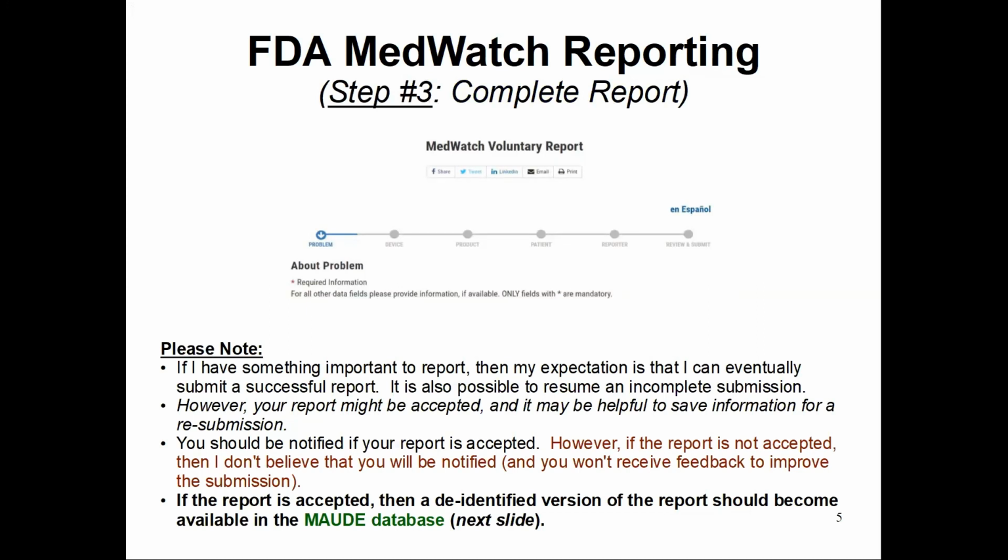And to be clear, the FDA does not want you to resubmit the same report again. So if it's been more than a few months and you haven't got notification it's been accepted, then you can consider thinking about ways you could collect more evidence or explain yourself better and resubmit. But I would take some time and think about what could be changed in the report. And the next slide will relate to the FDA MAUDE database, which is where, if the report gets accepted, a de-identified version will be posted publicly.